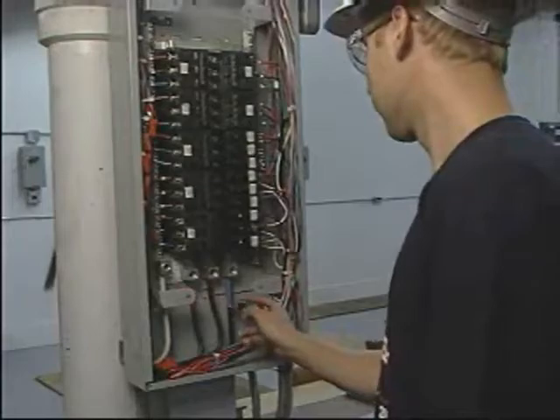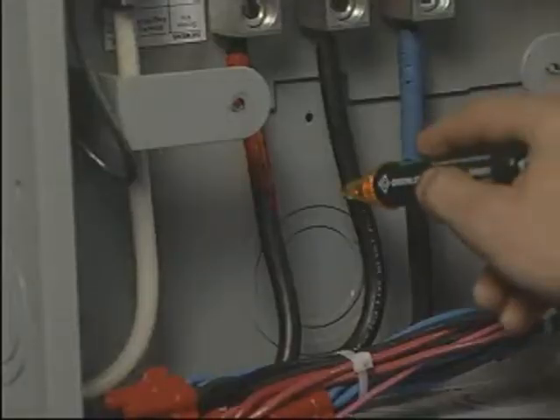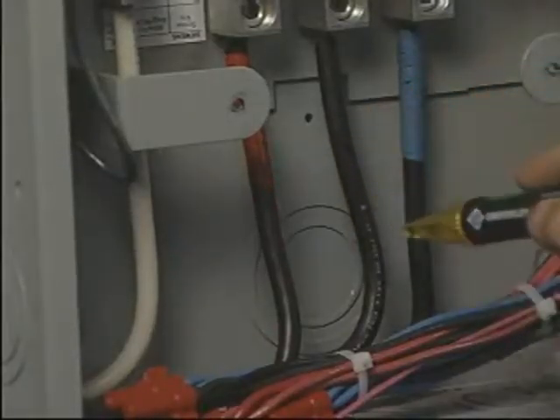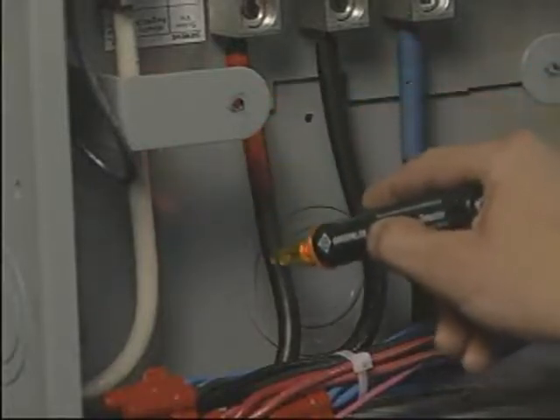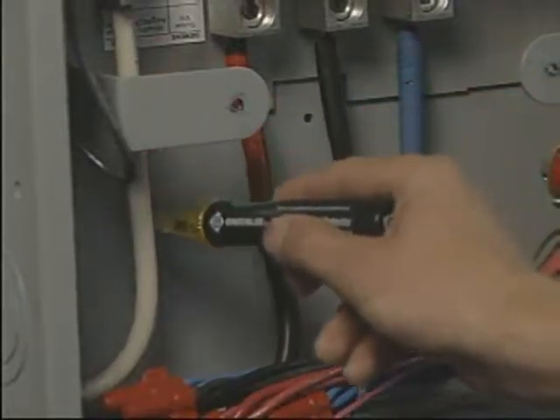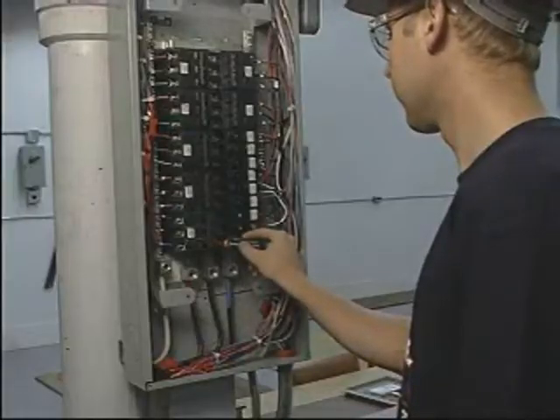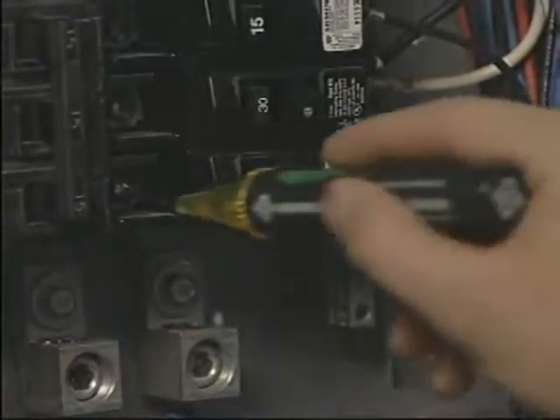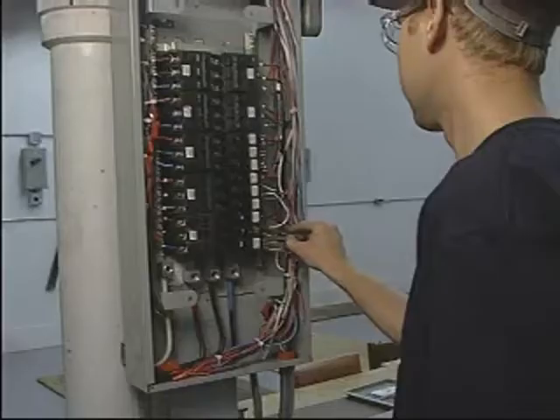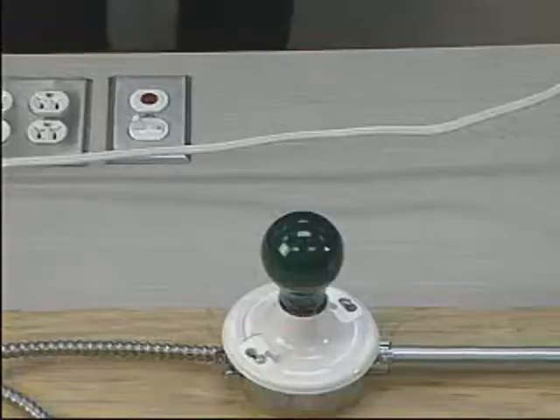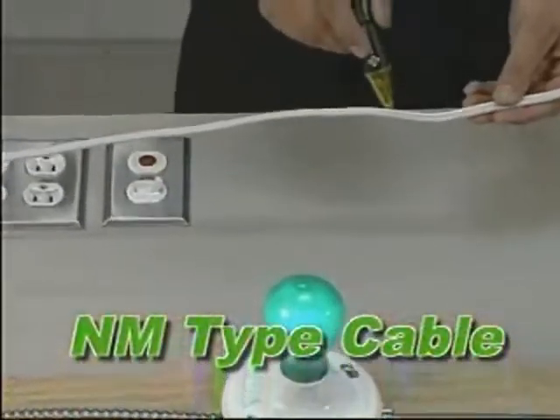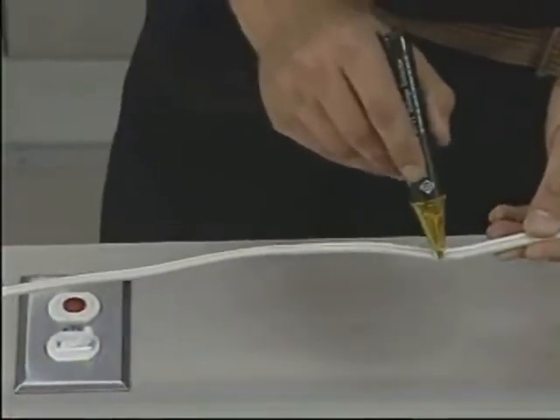When testing a breaker panel, check incoming phase conductors. You should get an audible and visual alarm. With the breaker on and checking the line side, you should get an audible and visual alarm. Checking the load side, you should also get the same alarm indication. With the breaker off, the line side should still get an audible and visual alarm. Checking the load side, there will now be no alarm indication. The GT11 is designed to identify the hot conductor, so always check both sides of non-metallic cable.